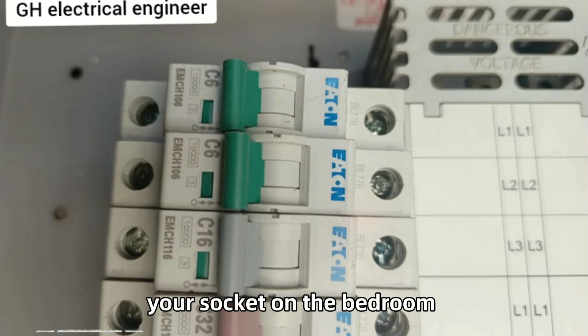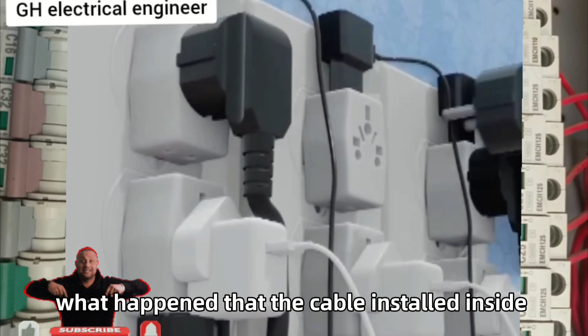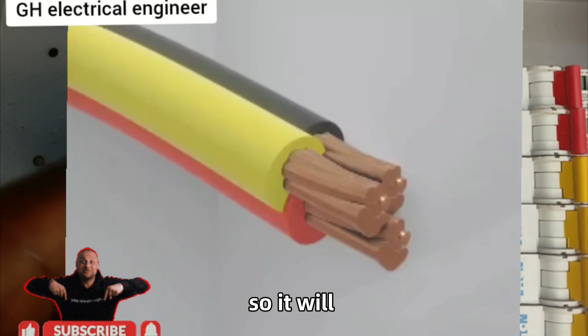Maybe you have a typical one bedroom with a small power point - like a socket in the bedroom - and you plug so many things into it. As you can see in this scenario, when you plug so many items in, the cable installed inside will exceed its limit, so it will melt, and as a result it will bring a fire outbreak in your property. These breakers are very crucial to save you from that overload, which is why they are designed for short circuit and overload protection.